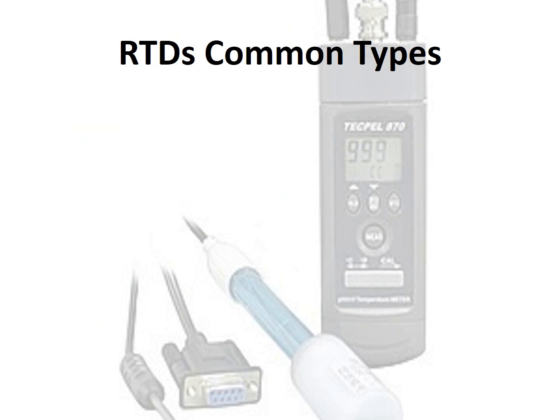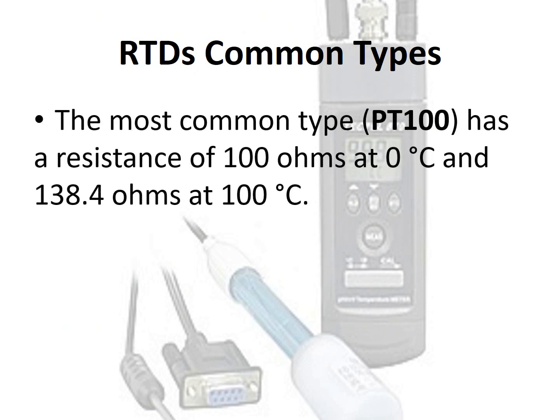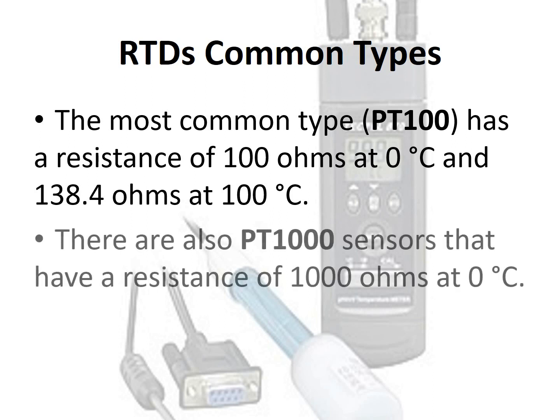The most common RTD type, Pt100, has a resistance of 100 ohms at 0°C and 138.4 ohms at 100°C. There are also Pt1000 sensors that have a resistance of 1000 ohms at 0°C.